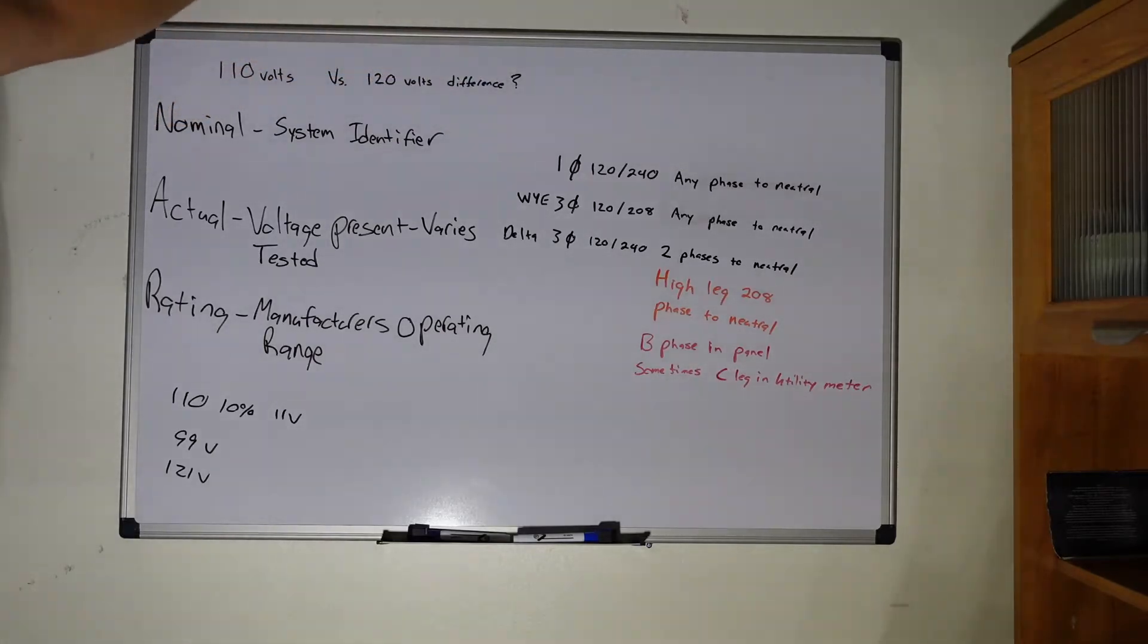On a wye three-phase 120/208 system, same thing, you can take any phase to neutral and that will give you 120. On a delta midpoint three-phase 120/240 system, two of those phases to neutral will give you 120, and then you have the high leg which is 208 phase to neutral.